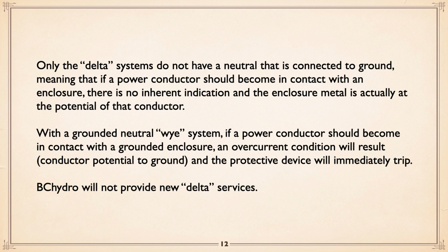With a grounded neutral Y system, if a power conductor should come in contact with a grounded enclosure, immediately that creates an overcurrent situation. Immediately you have a dead short. And that overcurrent situation, conductor potential to ground, means a protective device will immediately trip. BC Hydro will not provide new Delta services in the province.